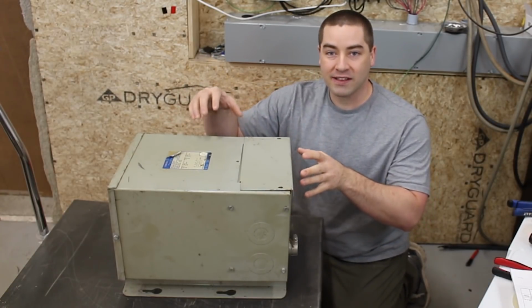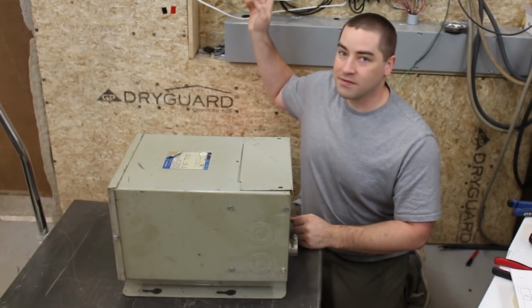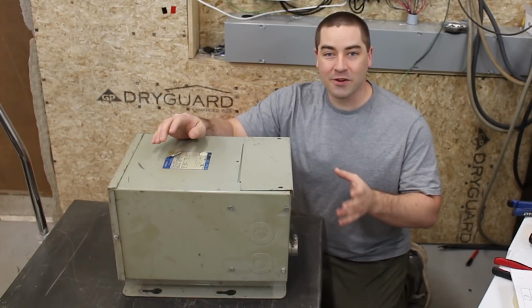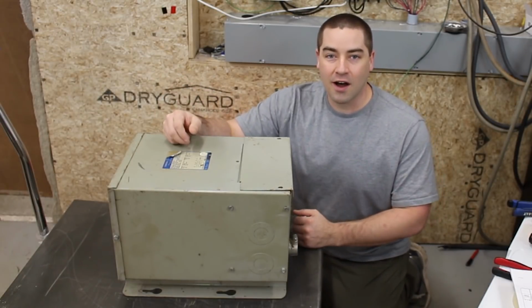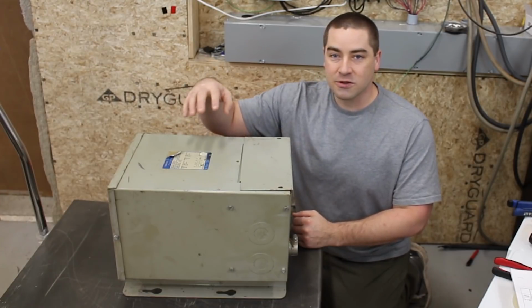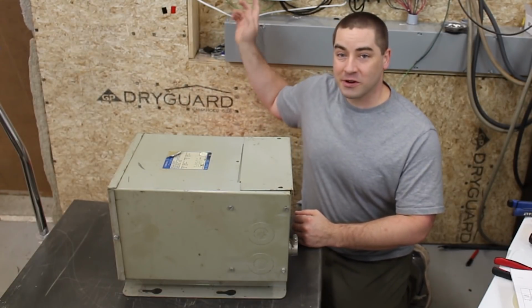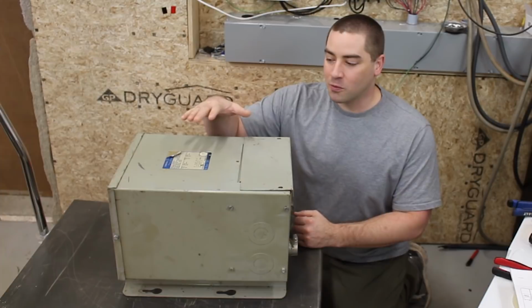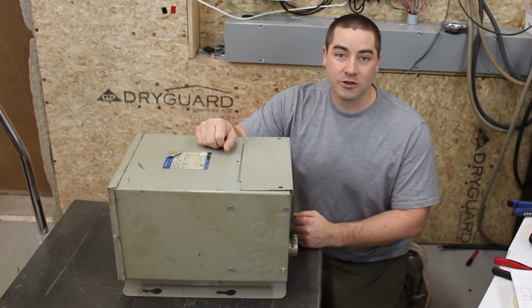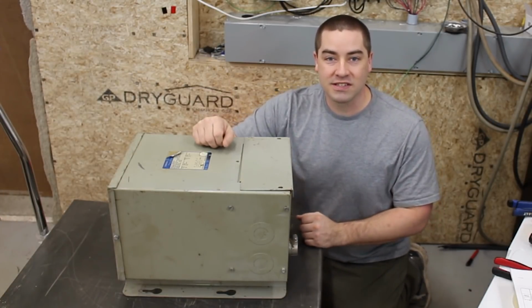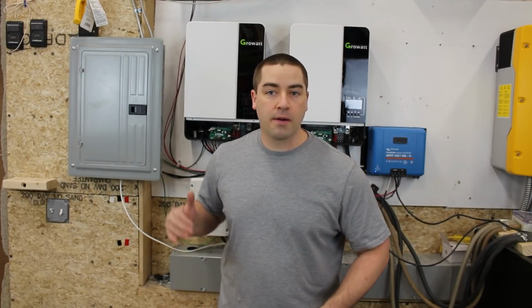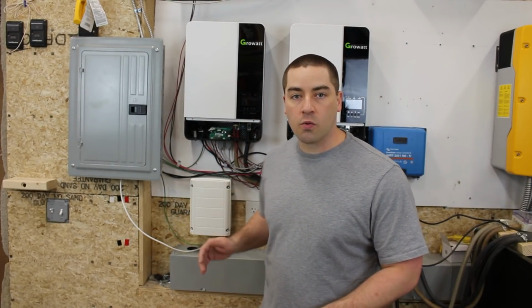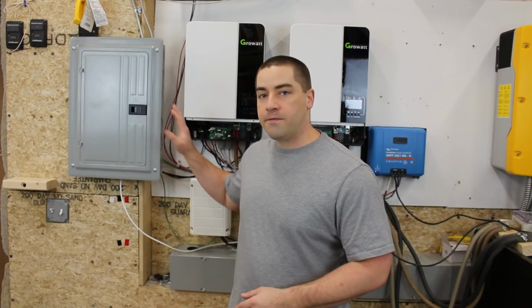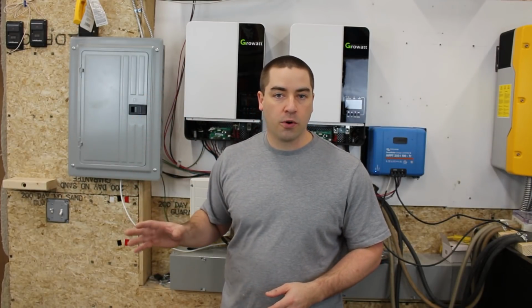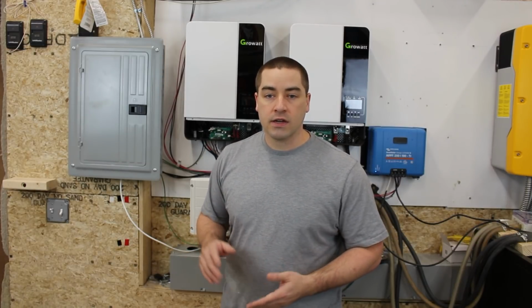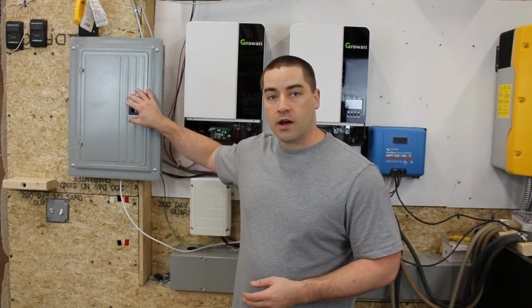So I can't wait to try out and test an isolation transformer instead of the auto transformer. So it's just another fun way of trying to build an off-grid solar system. And this will probably have more losses than the auto transformer, so I probably won't want this running all the time, but it's something that I want to try and actually measure and see how much the idle losses are going to be. A couple of other things to note about this setup. Currently, I'm only switching one of the hot legs and the neutral. When I feed this panel, it needs to be fed with a 2-pole breaker breaking both of the hot legs. So that could be done with back feeding one of the breakers on here.